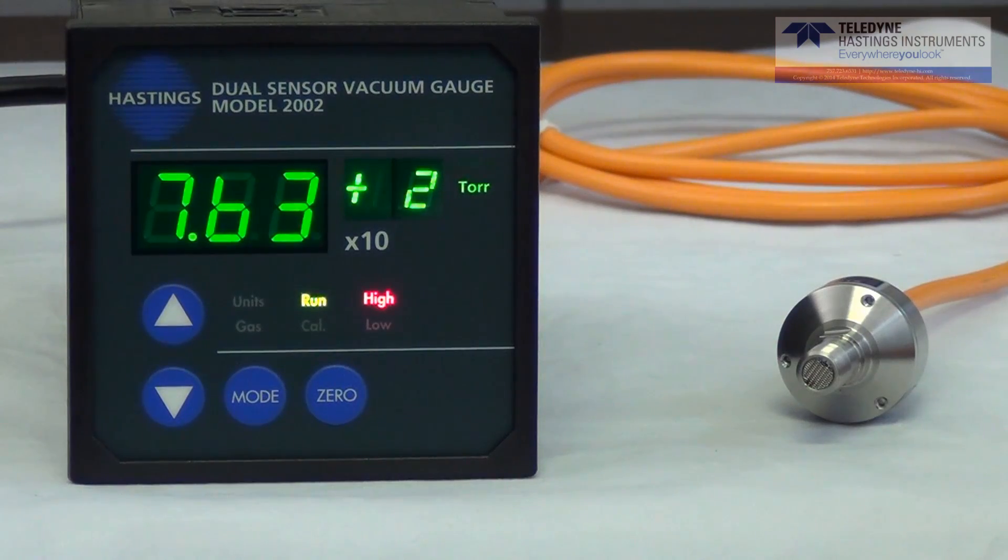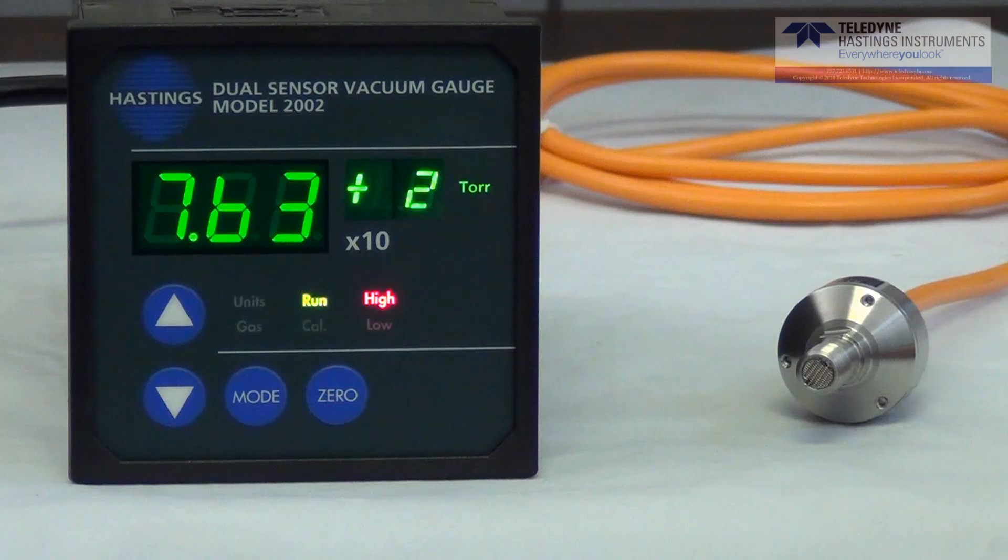One other cool feature about the 2002 is that the microprocessor uses the output from the lower pressure thermal sensor to automatically update the zero of the piezoresistive sensor. This gives the user the added benefit of improved accuracy, especially when venting the vacuum system.